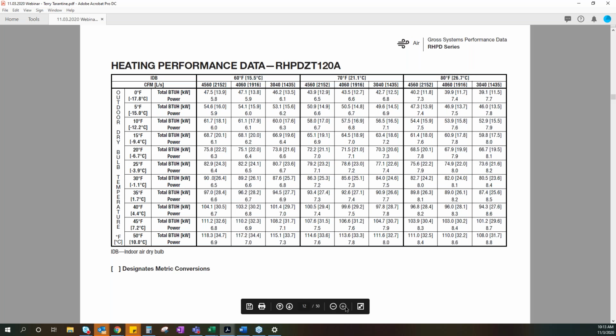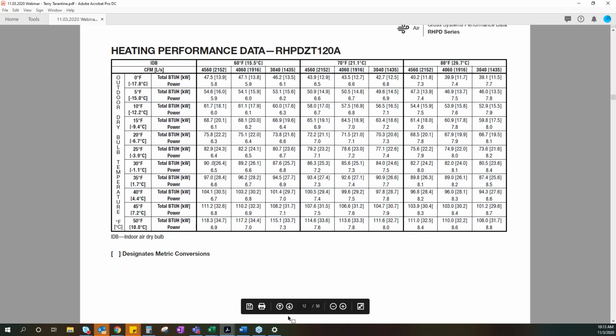All right, a little bit of an eye chart here, but if you look, there we go, perfect. This is a new 10-ton heat pump packaged unit, a rooftop type system. If you look along the top, you'll see 70 degrees. We'll take that middle point at 5, which is the second column down. So at 5 degrees with the 70-degree indoor air temp, we're getting about 50,000 BTUs out. That's less than half the capacity of the cooling system.